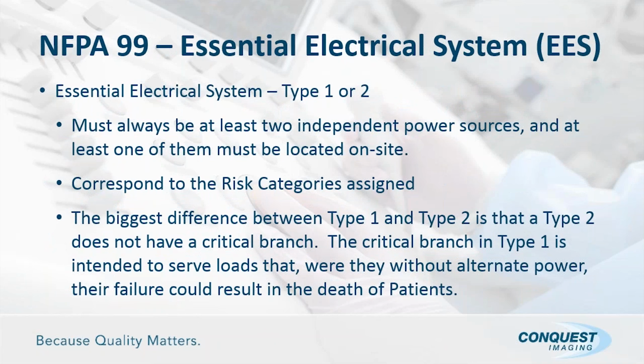After you talk about risk categories, there are also what they call essential electrical system categories. There's type 1 or type 2. And what this essential electrical system says is that you have to have at least 2 independent power sources, and at least one of them must be located on site. We all have different main power supply companies in the area. For example, in California, we have Pacific Gas and Electric Company, and that could be one independent power source coming into the hospital. But in addition to that, you'll have to have a generator located on site that can provide power in the case of electrical failure outside. So we want to be careful, or be aware of that.